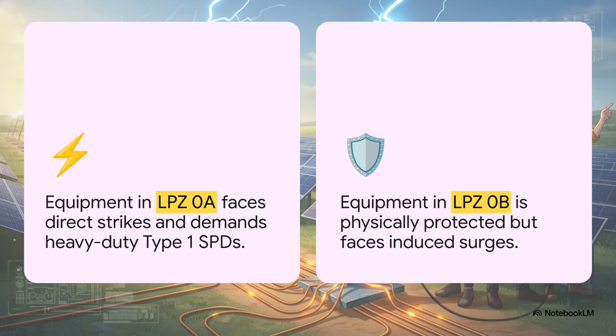Notice the very clear boundary distinction here. Any equipment sitting outside in the wide-open LPZ0A zone is in the direct strike area. It takes the absolute full brunt of the lightning current, so it absolutely demands a heavy-duty Type 1 SPD. Conversely, equipment sitting in LPZ0B is safely tucked under the physical cone of protection of your air terminals. It won't take a direct strike, right? But it still faces massive induced electromagnetic surges. So for that, you need either a Type 1 or a combination Type 1 plus 2 SPD.